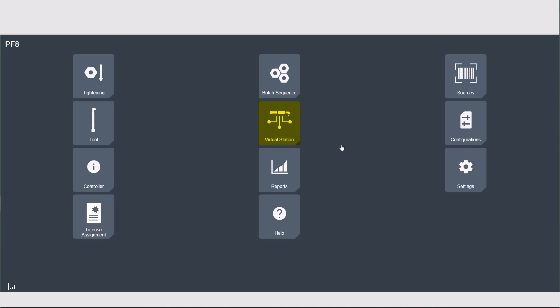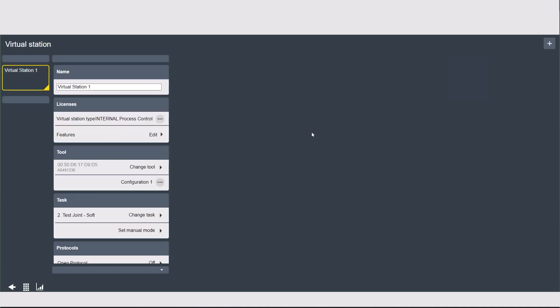The virtual station tab is where the other settings and configurations of the controller come together to create a unique station so that each tool connected to the controller can be configured exactly how you need for the specific application. When you first open the tab you're going to see that the software already has one virtual station created with the default name of Virtual Station 1. The PowerFocus 8 can support up to 20 tools using virtual stations, so when you need to connect another tool to the controller you're going to use the plus button in the top right corner of the screen. This will create another virtual station for you to configure and connect another tool.